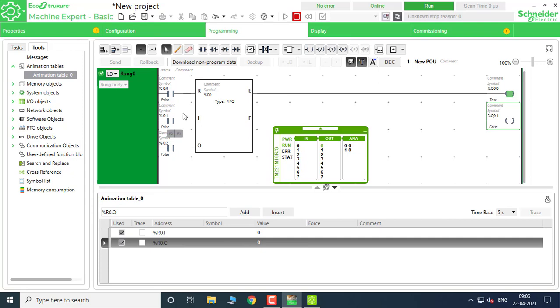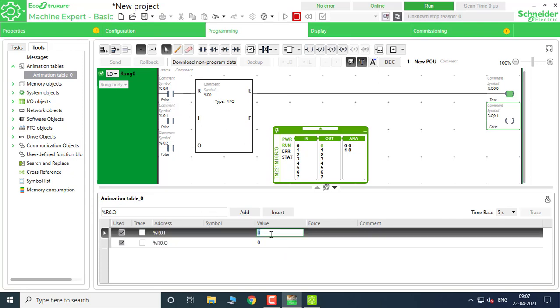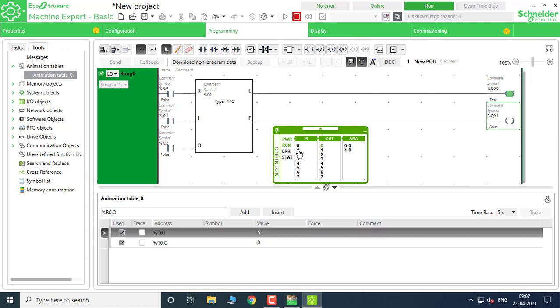At runtime, I have to first feed the value 5 and toggle the input I0.0. I input the value which I fed to %R0.I. You can see the Empty bit of the FIFO register has been set. I toggle it 1 and we can see the Empty flag is gone because 5 has been entered into the FIFO. Then I toggle it back, change the value to 10, and toggle again.